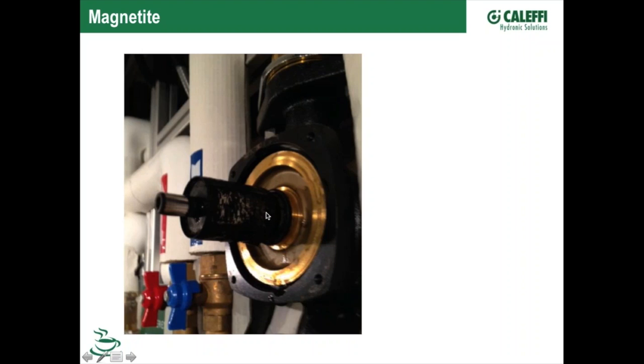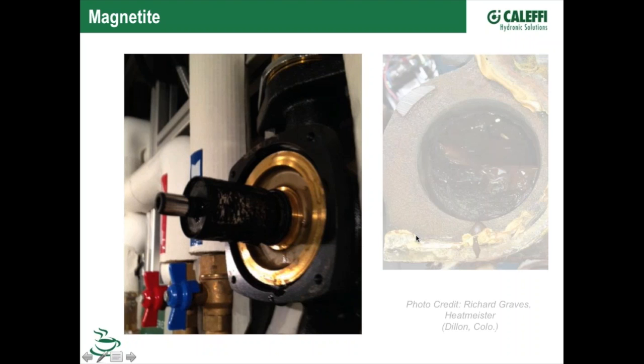So this is a little bit harder, a little bit trickier to get out of a system. It's hard to filter this out with a media because it's a very fine particle. It's almost like if you took just a carpenter's pencil or a lead pencil and sharpened it with your knife on your workbench or on your table, that's the type of deposit we're talking about. Really fine. Sometimes it'll have a greasy feel to it, picking up what's inside the system. But what you can do, exactly what's happening in this picture, is you can attract it to a magnet. So if we put a magnet on a device in the system, we're going to try and collect that stuff before it gets into harm's way there.